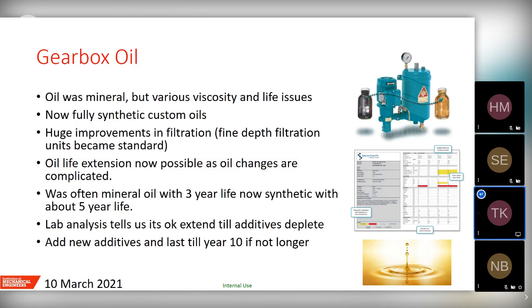So what we find now is the suppliers are offering additive top-ups, specifically made for the turbines, that you can put in, and that will extend the life. And now we're looking at sort of a 10-year life. And if you think about it, most turbines are planned to last at least 25 years. That's the sort of life we're looking at. So if you get to, say, 12 and a half, then you only have to do this once. And suddenly that is a massive cost saving and a massive health and safety improvement as well.